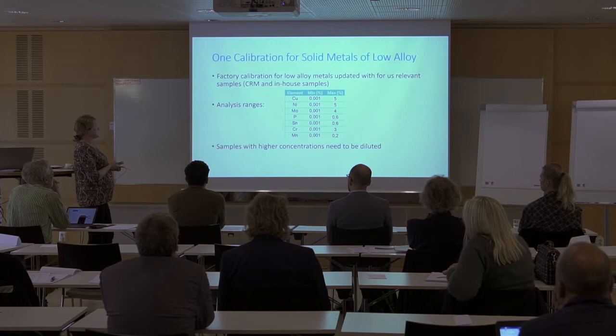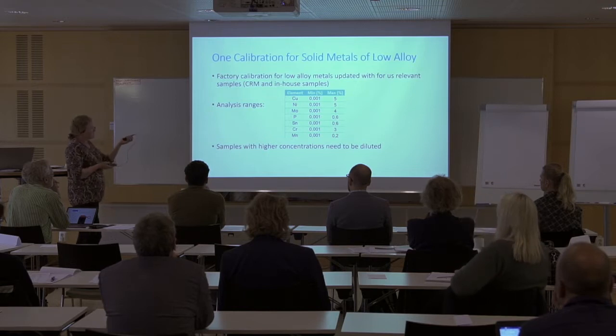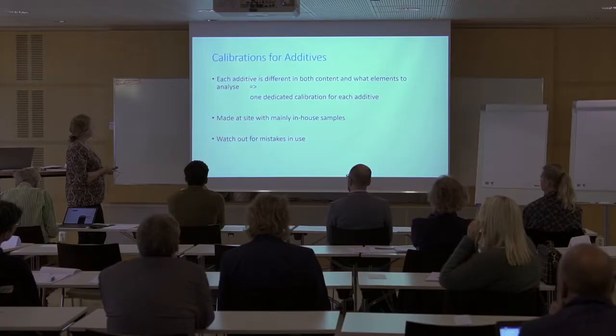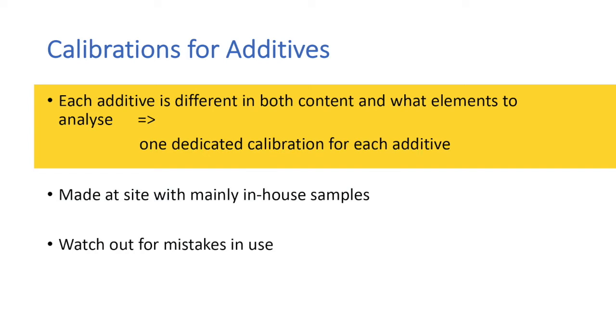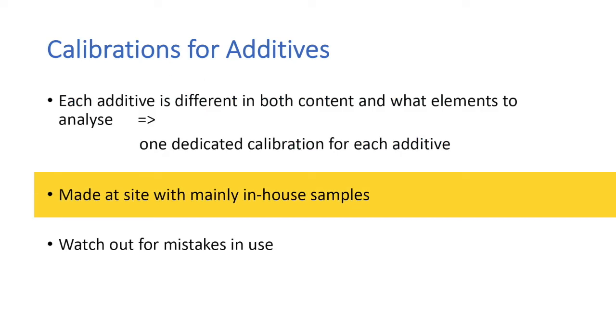Samples with higher concentrations need to be diluted. Yes, if we have a copper sample with 20% in it, we have to dilute it with pure iron, and then we can analyze it with this calibration as well. And then we have the calibrations for additives. Each additive or raw material is different in both content and what elements to analyze, so we have one dedicated calibration for each additive. And in this case, we have made it at site with mainly in-house samples because, yeah, it's for us.